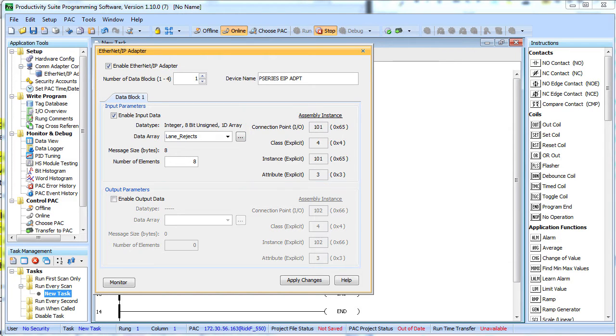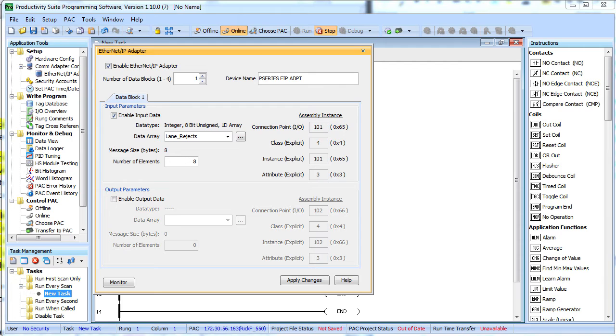Well, that's it, we're done. As soon as we transfer this program to the Productivity 3000, scanners will be able to connect with us and start getting periodic updates at the rate they request and remember this runs completely in the background so we just forget about it. All our program has to do is maintain that array of data. The Productivity 3000 takes care of pushing that data out to the scanner for us at the rate it requested.